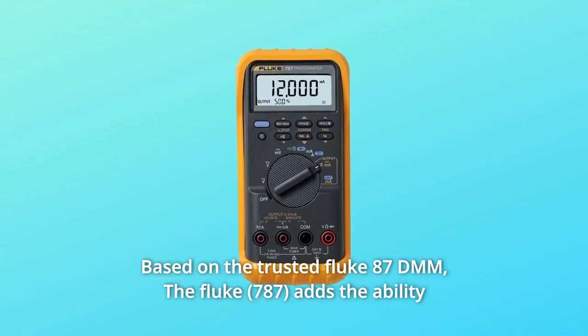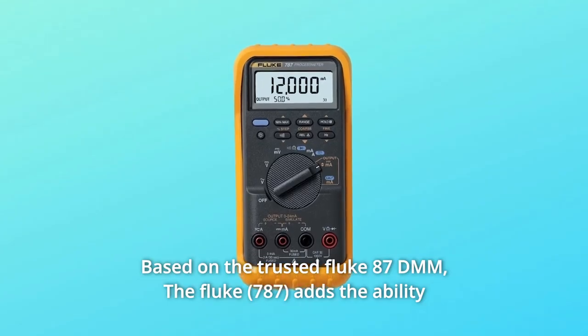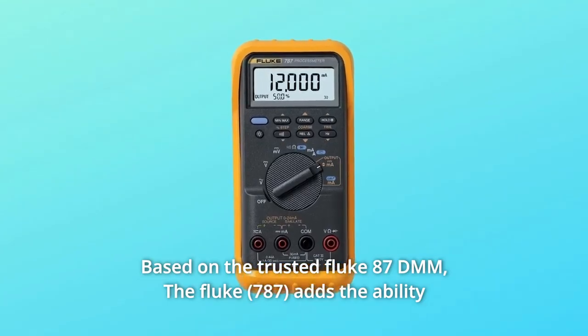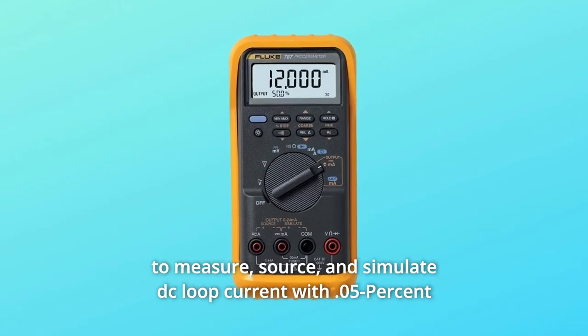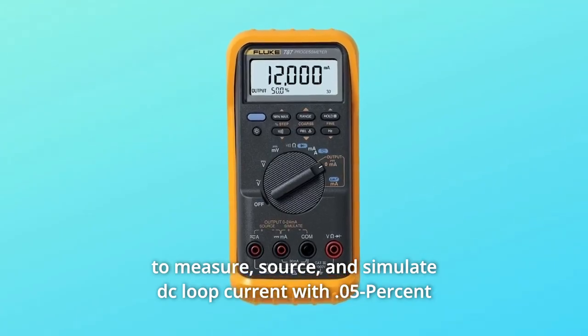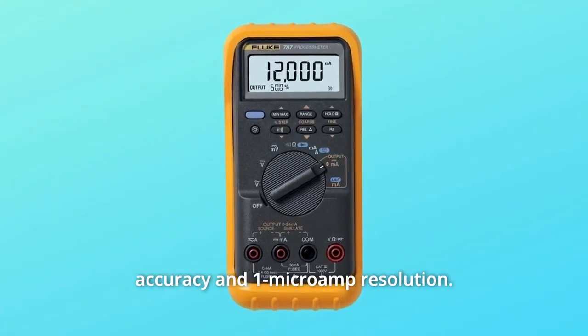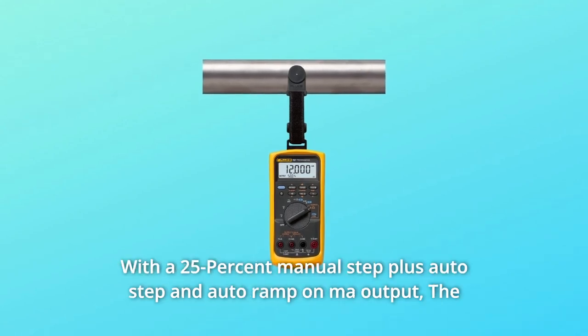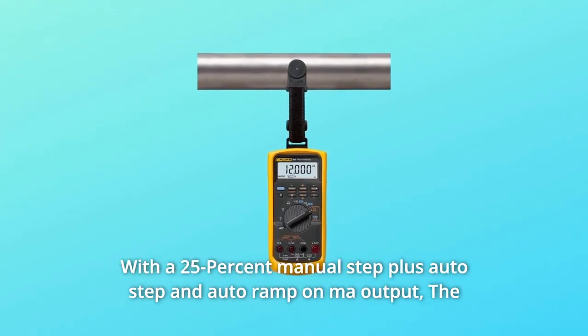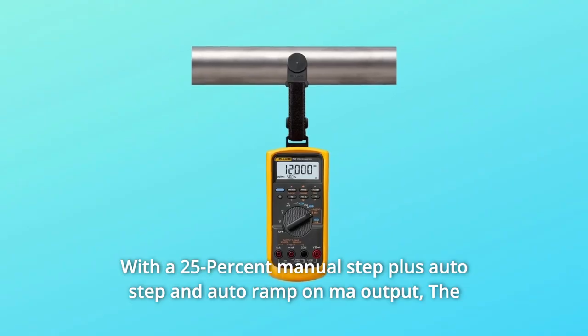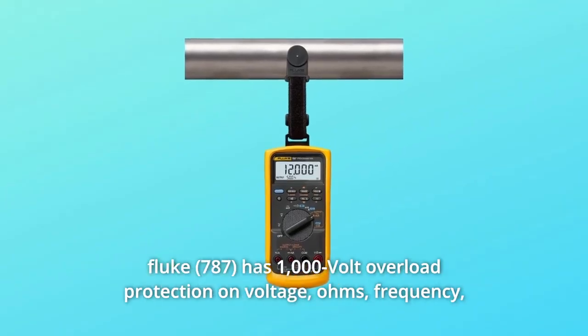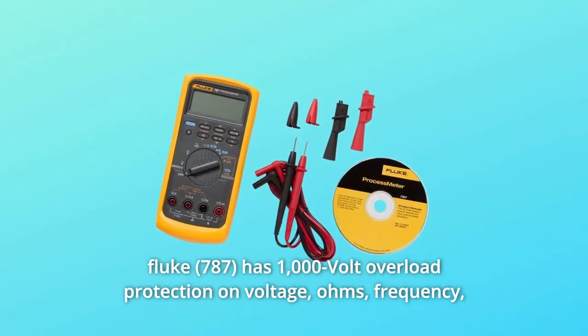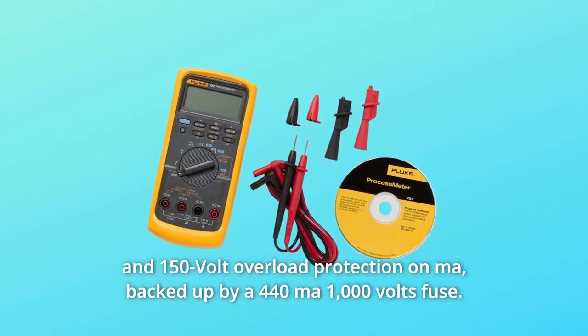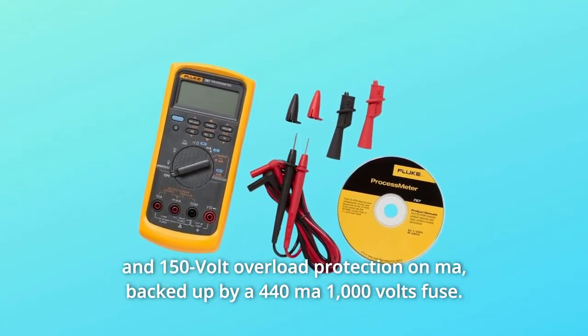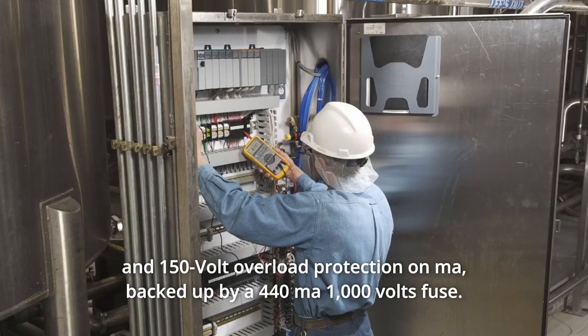Based on the trusted Fluke 87 DMM, the Fluke adds the ability to measure, source, and simulate DC loop current with 0.05% accuracy and 1 microamp resolution, with a 25% manual step plus auto step and auto ramp on mA output. It has 1000 volt overload protection on voltage, ohms, and frequency, and 150 volt overload protection on mA, backed up by a 440 mA 1000 volts fuse.